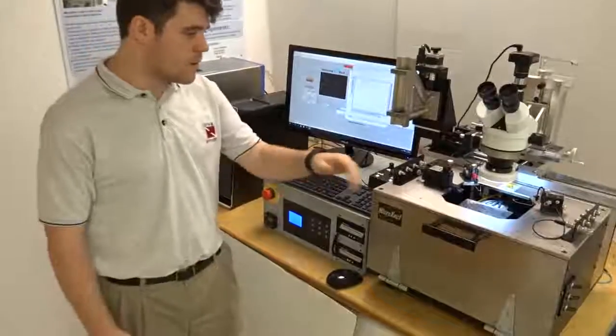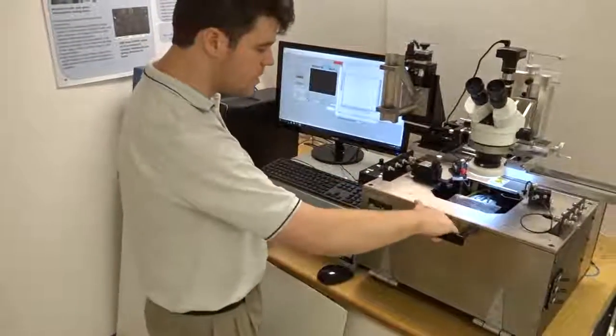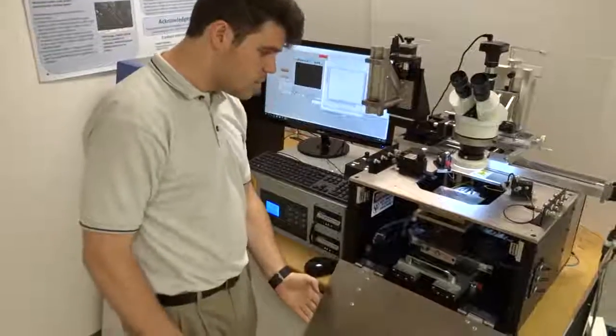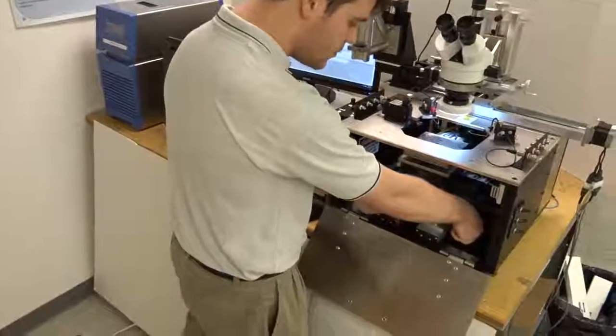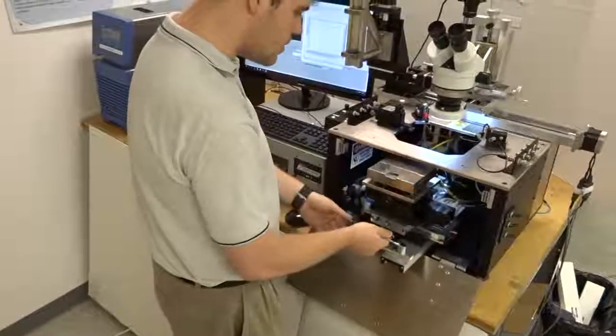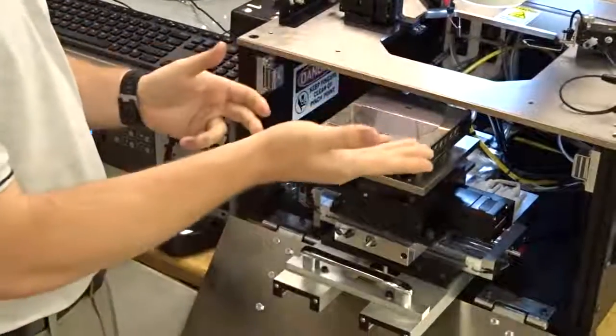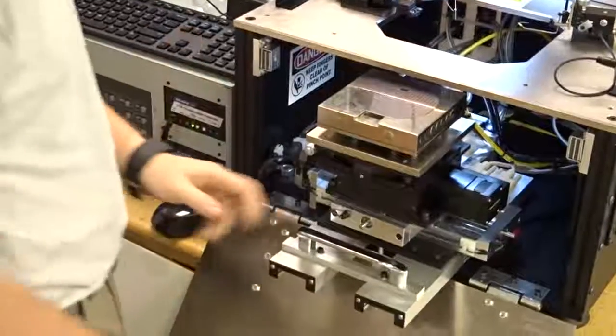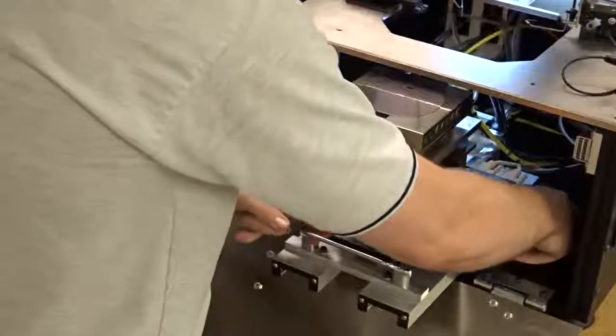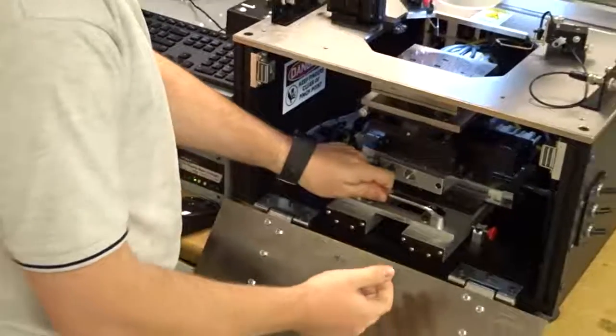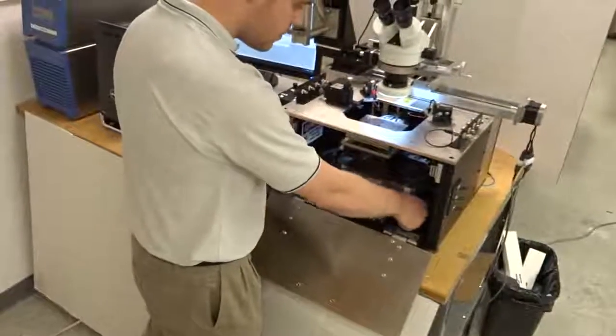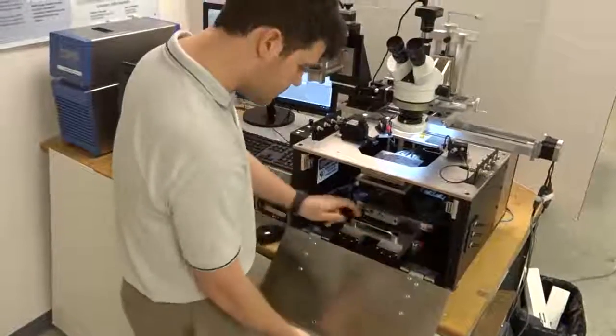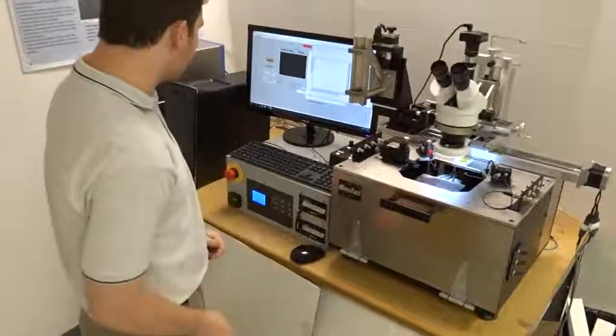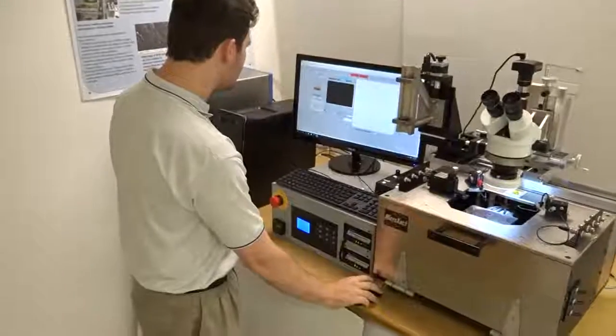The user has now, on this side, got the system ready. We can open up this here, which will allow us direct interface. By loosening the screw here, we're able to open, tighten back, and then put a wafer onto this instance here. For this, we're using our standard test wafer that we have a wafer profile for. We are then going to take it and move this back in. You'll notice that it stops right here as a solid stop, so every time this alignment happens perfectly. We then close this back up, and we can move into our homing position.